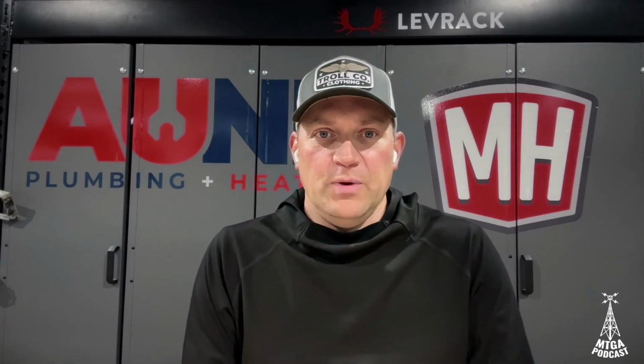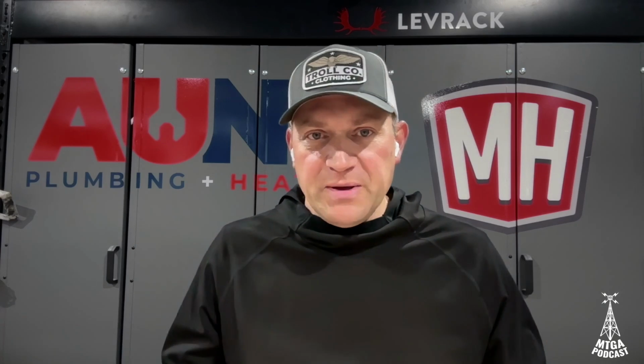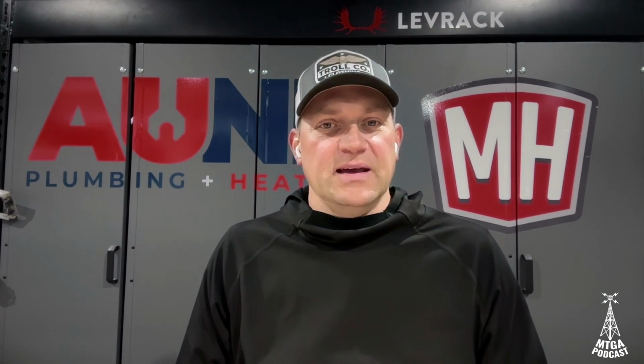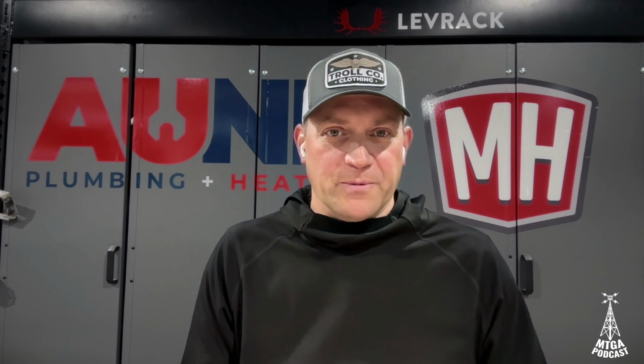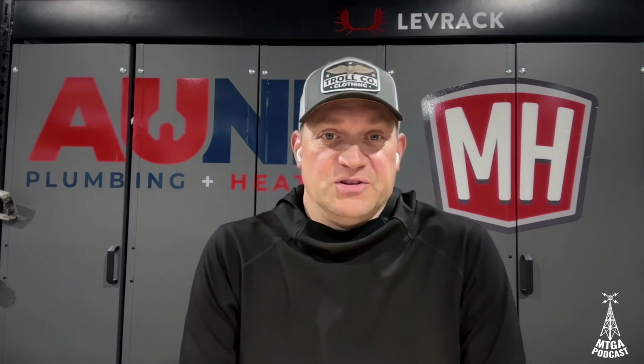Well, and we're seeing this in the Missoula area, a number of customers that have been told for a couple of years now, you can't go high efficiency with your baseboards, or you can't do this, or you can't do that. And we're capitalizing on that, saying, well, yes, you can, because without too much modification, I could chop out that old baseboard and put in a Smith HE2 that's got twice the output, or the same output, but at 135-degree water instead of 180. Or put in some Runtal or a Meissen panel radiator. There's all kinds of options. All of a sudden, we can take this house that was never built for low temperature operation, and with a little modification, make it ready for low temp applications. And then the heat pump is just ripe for that.